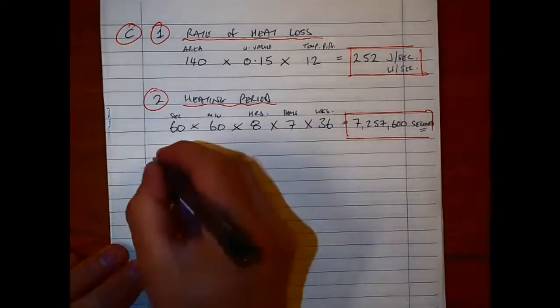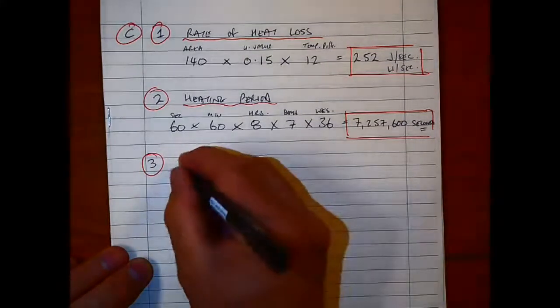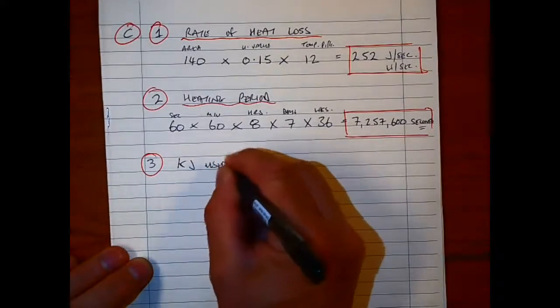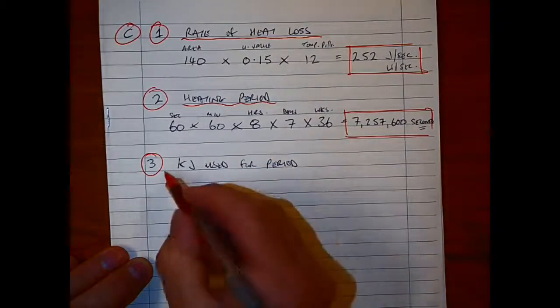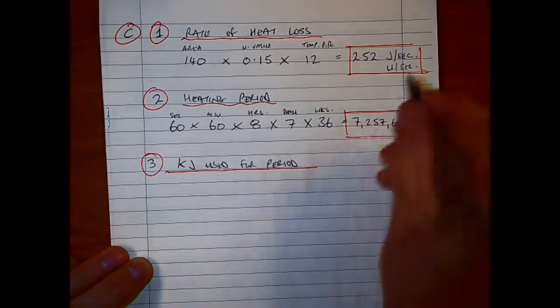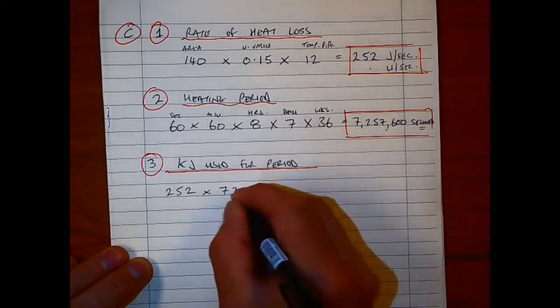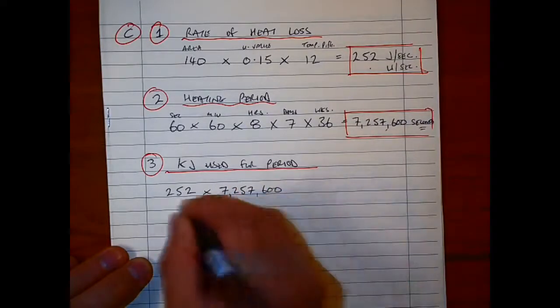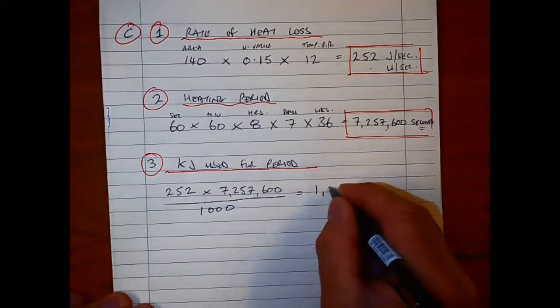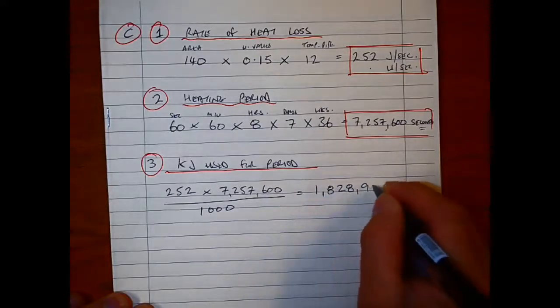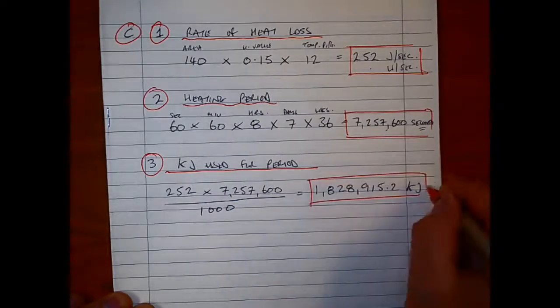Now, because I've got seconds in the heating period and the rate of heat loss, I can use the two of these here now to calculate the amount of kilojoules that are used, because it's joules per second that we have from our first calculation. There's two parts to this here—if you wanted to, you could work out just the joules and then take the kilojoules. I'm just working it out in one here to get the kilojoules used for the heating period. So 252 multiplied by our 7,257,600 seconds, put that over a thousand, and calculate that out. It's going to give us another fairly large figure of 1,828,915.2, and that's kilojoules. That's all important—directly kilojoules.